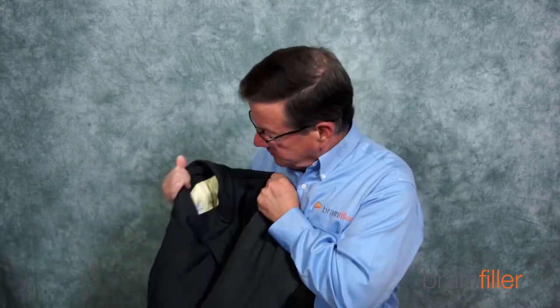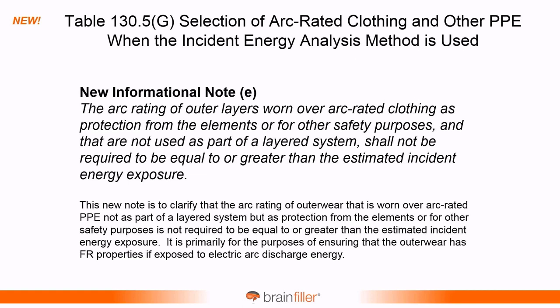And so this first change is, if you're wearing arc-rated PPE like this, this is a 65 calorie PPE, and you have the need to wear an outer garment, either for weather to protect you from the elements, or maybe for safety, like a high-vis vest or something like that. What this new informational note is designed for is that you can wear those types of garments as long as they have an arc rating, and the arc rating doesn't have to match what your actual protection requirement is. So the objective is, if there is an arc flash, just to make sure the garment doesn't ignite and keep burning. That's what it's all about. This is actually your primary protection. There have been a lot of questions about that over the years, and that was a change made to the 2021 edition of NFPA 70E.